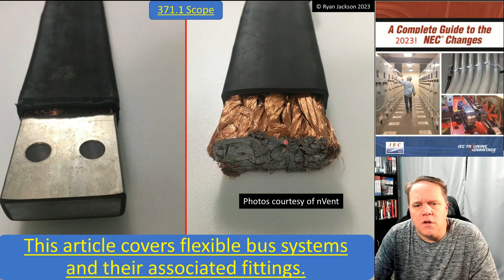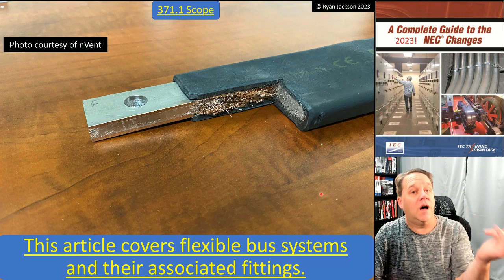Now, you're not just going to run this stuff up in a ceiling. It's insulated, but it's still a bus bar, so you're not going to be wiring a small building with it. This is to move a lot of current from point A to point B. You're not going to go from a little 200 amp panel to another 200 amp panel with this. This is like something where I want to go from a transformer to a switchboard with 4,000 amps or something.